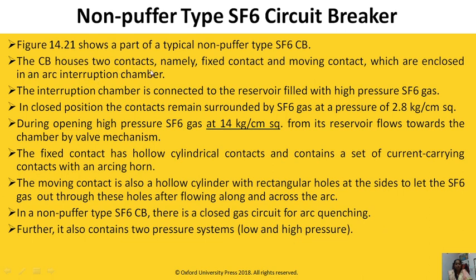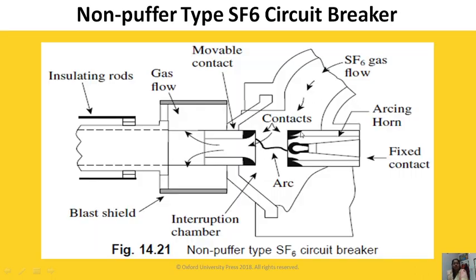The circuit breaker houses two contacts — a fixed contact and a moving contact — which are enclosed in an arc interruption chamber. The interruption chamber is connected to a reservoir filled with high-pressure SF6 gas. In the closed position the contacts remain surrounded by SF6 gas at a pressure of 2.8 kg per centimeter square. During opening, high-pressure SF6 gas at 14 kg per centimeter square flows from the reservoir towards the chamber by a valve mechanism, and the arc gets interrupted.